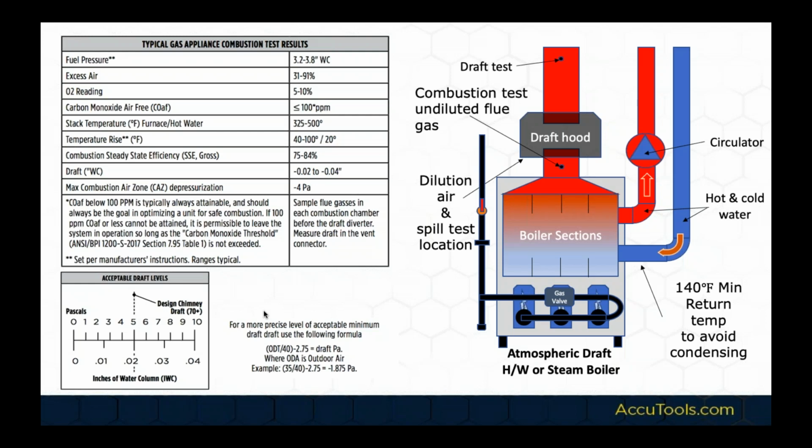Again, about the same steady state efficiencies. One thing I will tell you, when you start up a cold boiler and it's full of cold water, the first time you start it for the year, a little bit of condensation dripping down on the burners is normal. You'll see the same thing with a brand new hot water tank you put in. A lot of times it's not leaking. In fact, 99% of the time it's not leaking. It's just condensation because the water's cold. And once the water gets warmed up, it's going to stop condensing and it'll run fine.